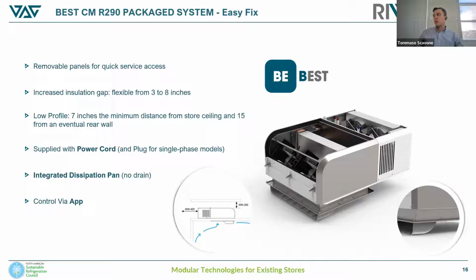So practically you are able to lower or increase the gap. Maybe if I can use my laser here, I can show. So this right here is the gap that I'm talking about, that practically adjusts according to the thickness of the panel. So if you have a thicker panel, you can extend, or if you have a smaller panel, it will be shorter, down to 3 inches. The air intakes also have been modified for increasing the airflow necessary to cool down the condenser and improving the efficiency, and allowing to reduce, even in this case, down to 7 inches, the minimal distance from the store ceiling, or down to 15 inches from the eventual rear wall behind the unit. So these monoblocks can be installed also in very tight spaces, but still performing well.